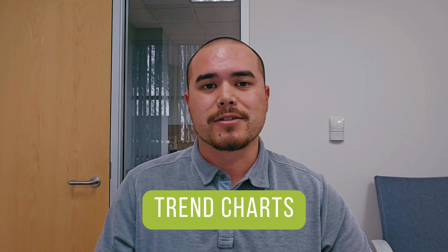Today we're talking about one of the most foundational tools you'll use in condition monitoring, trend charts. So what are trend charts? In simple terms, they track how certain parameters like vibration, temperature, or speed change over time. This is incredibly valuable because machines rarely fail suddenly and all at once. In most cases, there's a gradual change, a small increase in vibration, a deviation in temperature, or some subtle shift in performance. A trend chart lets you see these changes before they become critical.